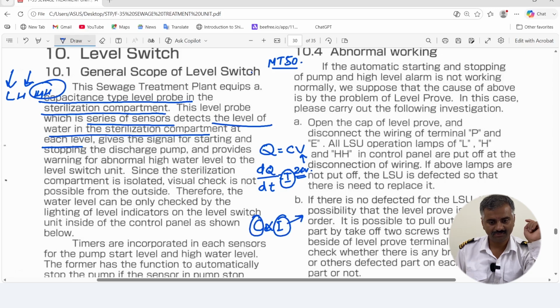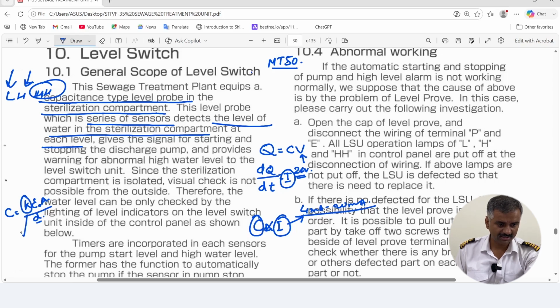So that is my signal for the change in current, 4 milliamps to 20 milliamps. Your values change, and according to that you have the signal for say low level, high level, or high-high level. So as capacitance changes, your current changes. So how does capacitance change? C is equal to K epsilon naught A upon d. So in this, the rest all remain constant. K is your dielectric constant. Now what is dielectric constant? Dielectric constant is a specific property related to the fluid.